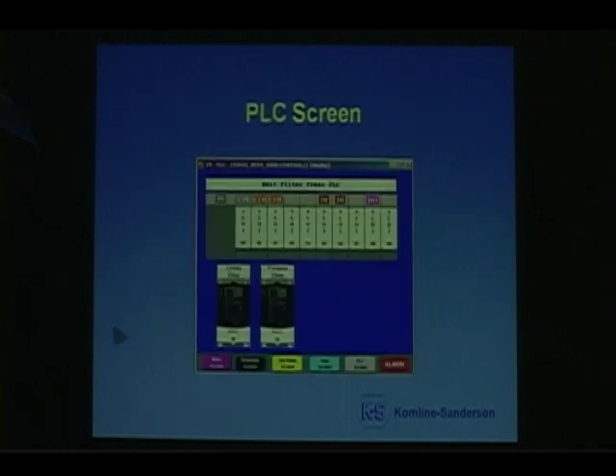This is called the PLC screen. The top portion is the PLC main control panel, and then the bottom half has the two gravity belt and the pressure belt VFDs. No longer do the maintenance, electrical, and IT guys have to open up the panel to troubleshoot the PLC or the VFD. I know previously on some of the panels we supplied, after about a year you open it up, it looked like a rat's nest. They don't have to do that. They can troubleshoot right from the OIT.